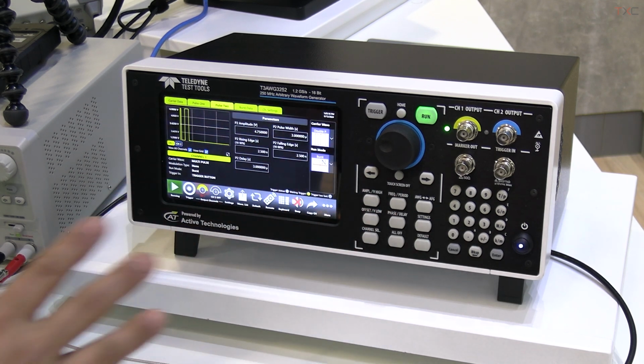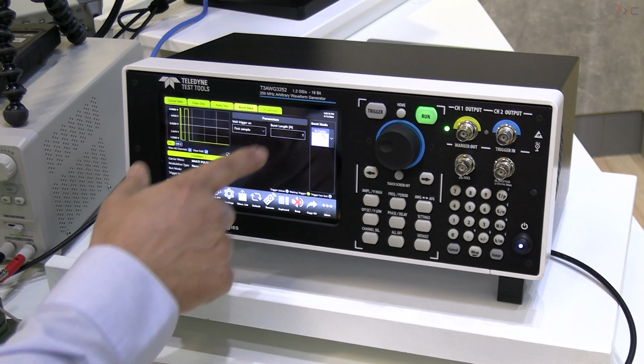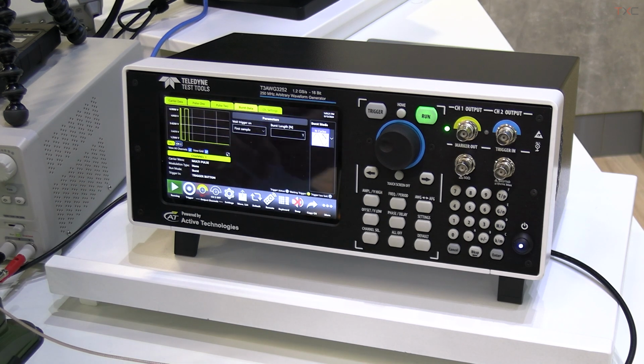Then the second pulse, the delay from the first to the second pulse, and again the amplitude, so you can control each of these parameters individually. And then I have set that for a double pulse into burst mode. I want to output just one burst when I click the trigger button to make a new acquisition, to make one test, so that I don't have the stress all the time on my semiconductor.